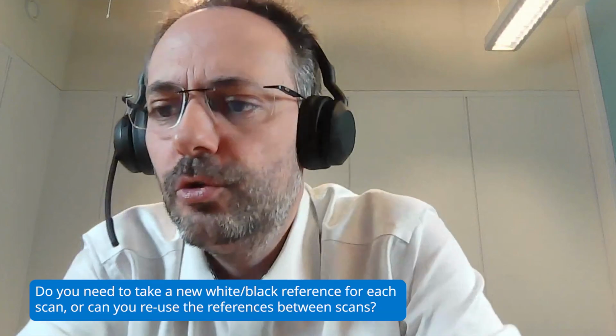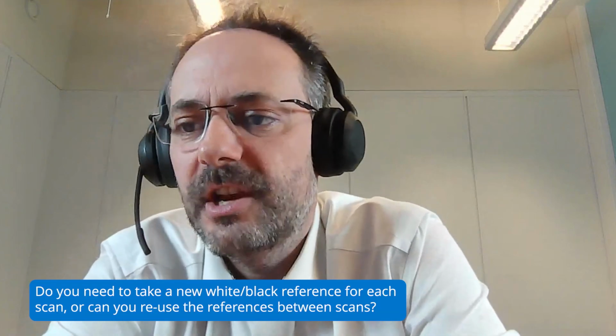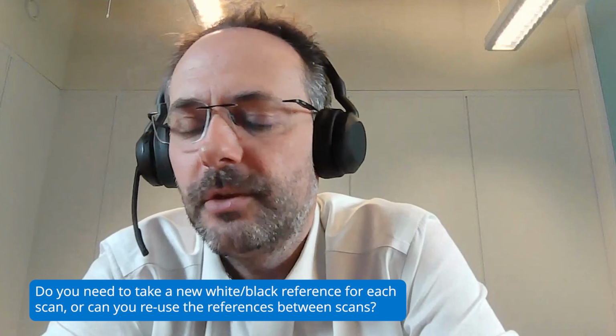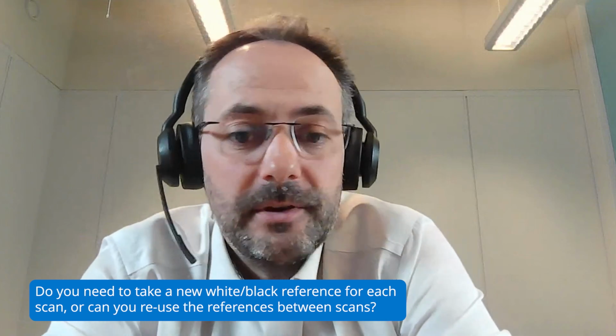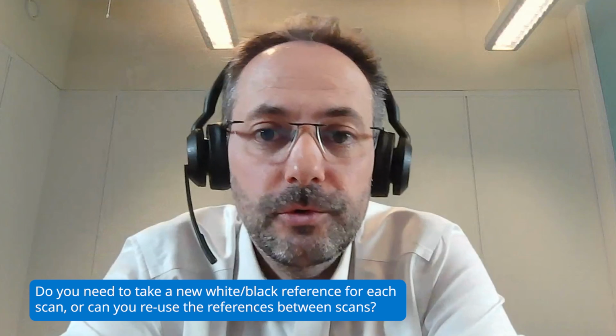So the question was, do you need to take a new white-black reference for each scan, or can you reuse the reference between scans? It depends on what you want to do, on what you want to test. First, you need to understand why you take the white reference and the dark reference. The white reference, you take it if, for example, you change your illumination or things like this. Basically, the white reference, you take it to measure the incident light.